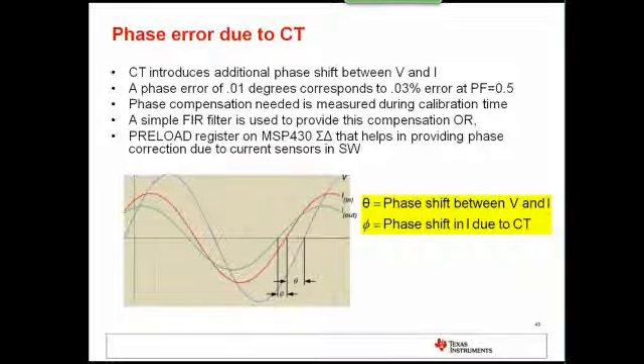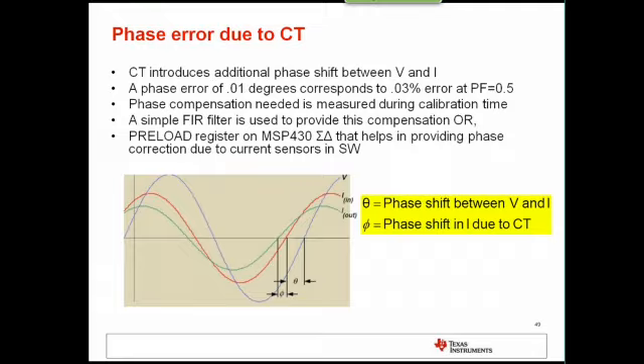Whenever you use the CT, there's an additional phase shift that is introduced. This could adversely affect accuracy, as I mentioned earlier. For instance, a phase error of 0.01 degrees could cause a noticeable difference of 0.03% at a power factor of 0.5. As a result, phase compensation is needed, and there are two ways to provide it. The first way is to have a simple FIR filter, and the second way is to use the preload register to delay the sampling instance of a particular converter with respect to other converters.